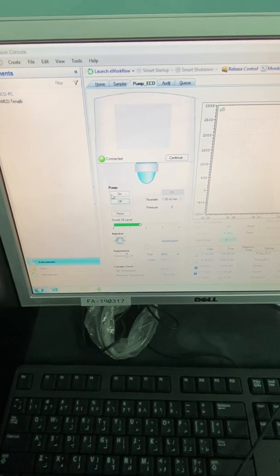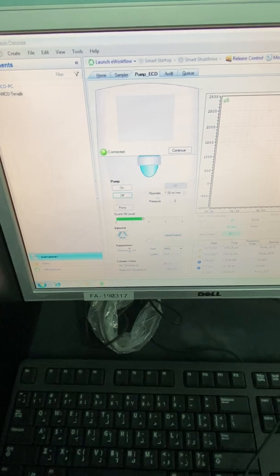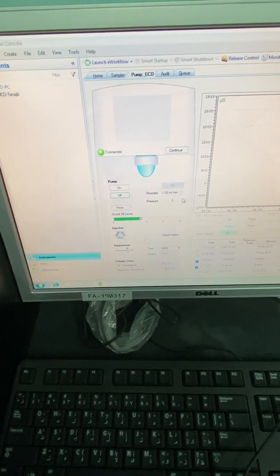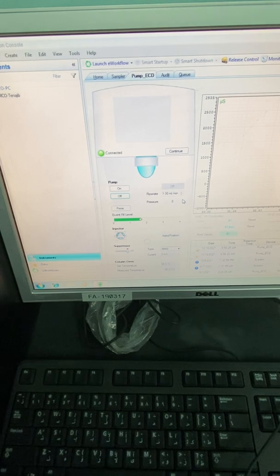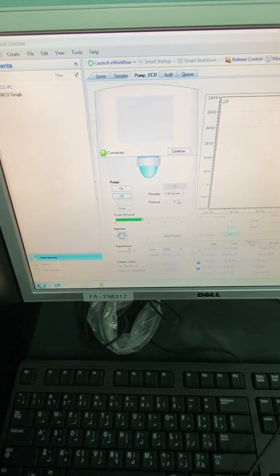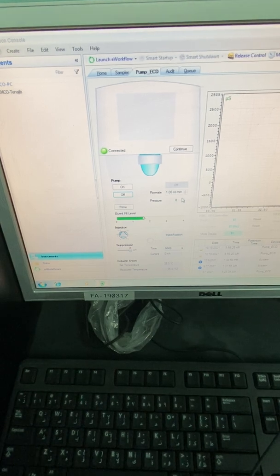From here, the main thing you want to make sure is that once you press the pump, based on your flow rate, you will have a pressure. And this pressure, as per your method, usually it's from 800 psi up to 1400 psi.